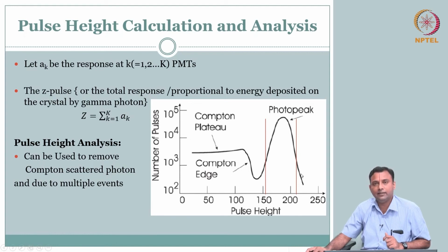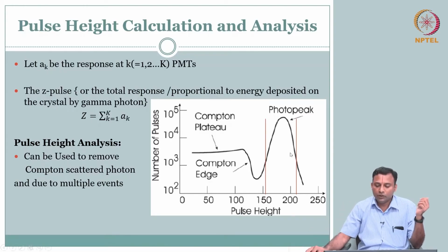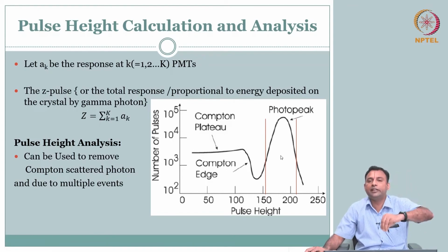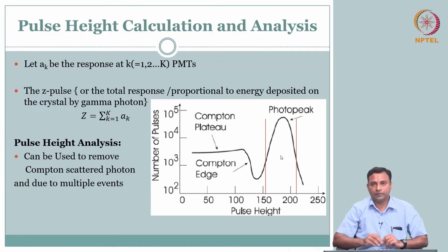What is this greater side? Sometimes you have multiple events simultaneously recorded, multiple events coming from different directions, multiple interactions. Sometimes if that happens, you get more signal, but then there is no meaning in saying which interaction you are talking about, because you cannot tease that out. So you have a region where, based on the energy, you can set the tolerance, and say that this scintillation is related to the radioactivity, meaning I can use this scintillation information to locate where it came from in the crystal, and therefore where it came from in the object.